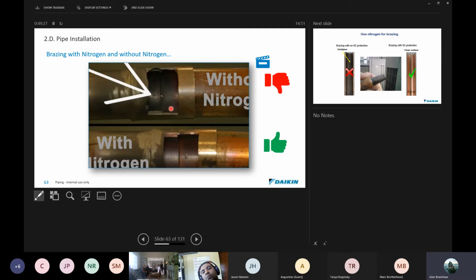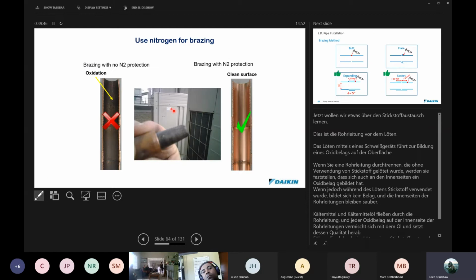When we inspect sites, it's one of the things that we can do. We can ask to cut open piping. And if we find that the piping has got evidence that it wasn't welded with nitrogen, this will affect the warranty of the unit. Something else to consider. Here's a clean surface and an oxidized surface of this over here. And like I said, there are strainers in the system, and these strainers are very, very fine. If you've ever cut into one of these strainers, you'll see it's a very fine mesh, and these can clog up. And we don't want to have that happening.